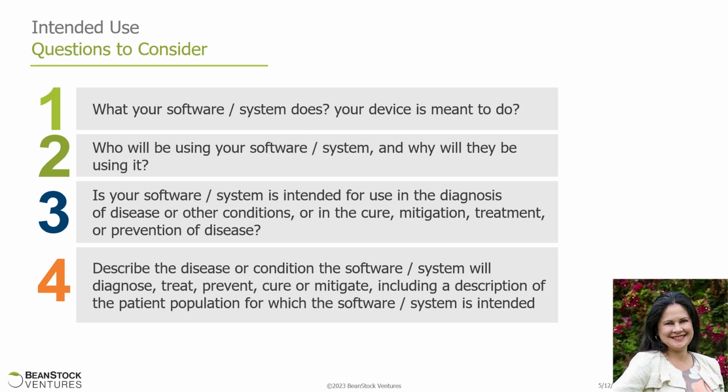Question number 1 is, what is your software system? What does it do? What is the device meant to do? Who will be using your software system and why will they be using it? Is your software system intended for use in diagnostic of disease or other conditions? And describe that disease or conditions the software will diagnose or treat, including a description of the patient population in which the product is intended.